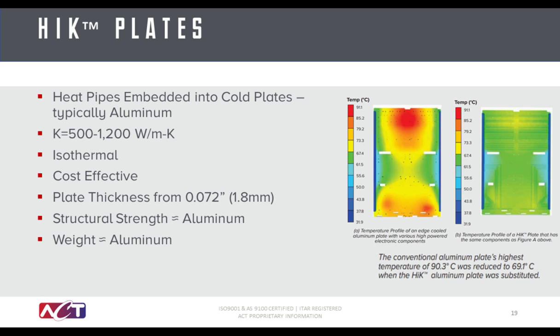Implementing these heat pipes in the aluminum plate increases the thermal conductivity, spreading heat efficiently to the most effective cooling location. Comparing against copper or aluminum base material: aluminum has a thermal conductivity of about 175 watts per meter K, copper 385 watts per meter K, but the high K plate technology reaches anywhere between 500 to 1,200 watts per meter K.